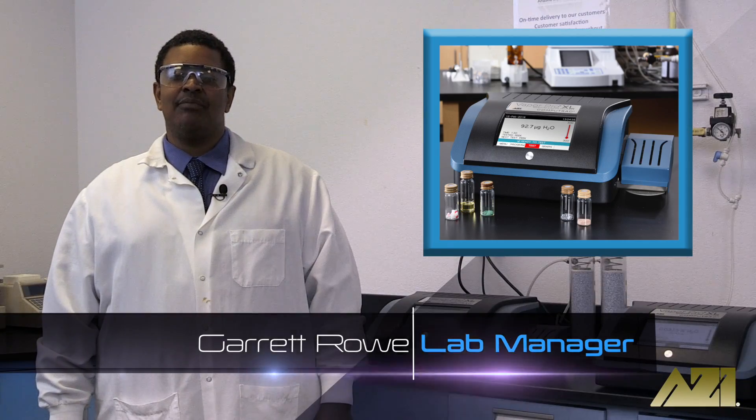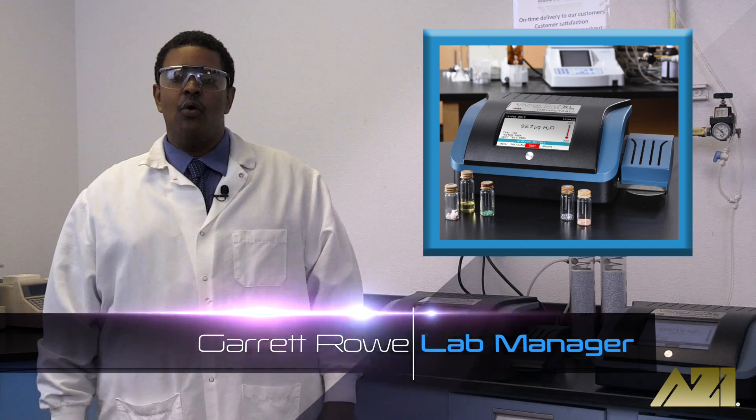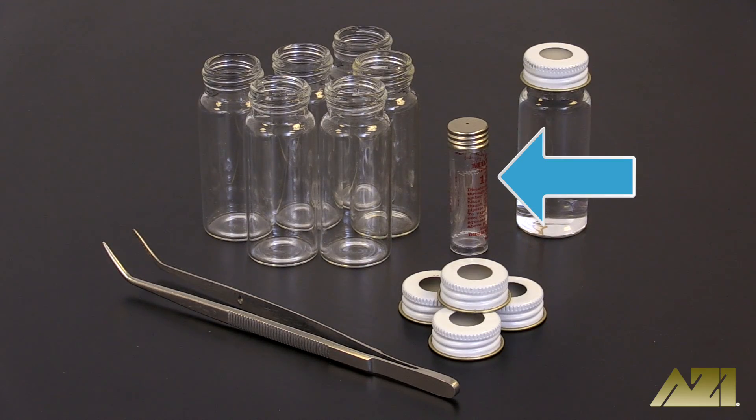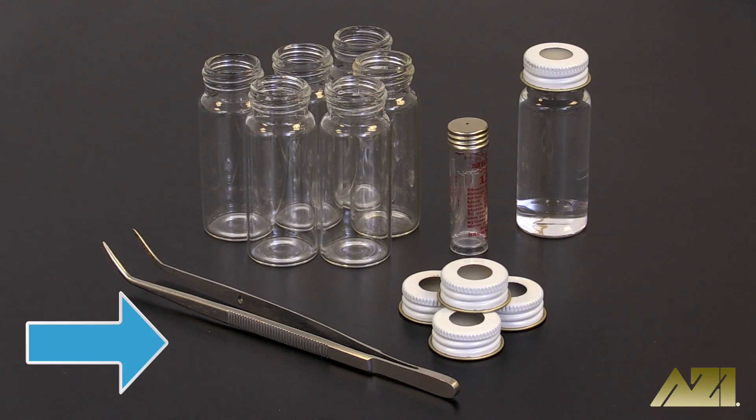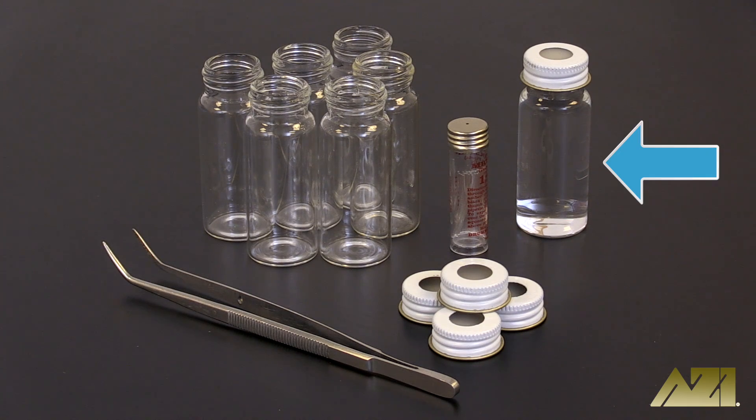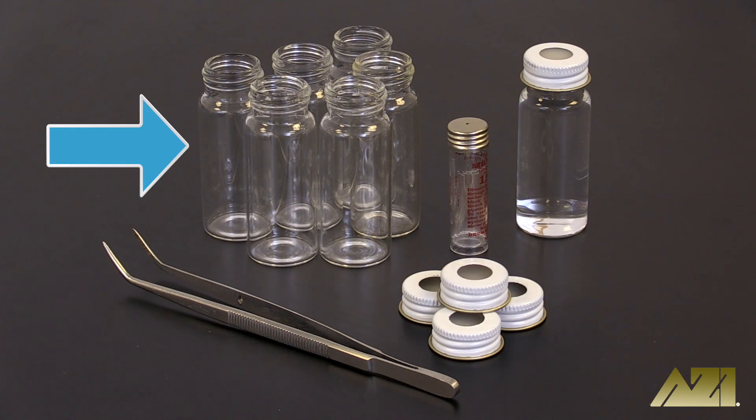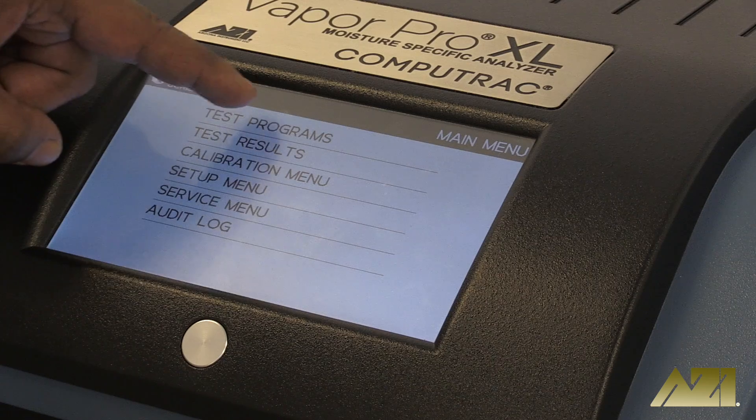To perform the system calibration on your new VPXL, you will need the following: one microliter microcaps, a pair of tweezers, a small supply of purified or deionized water, and sample bottles, caps, and septa. All of these items can be purchased through Arizona Instrument. See the description below for more details.